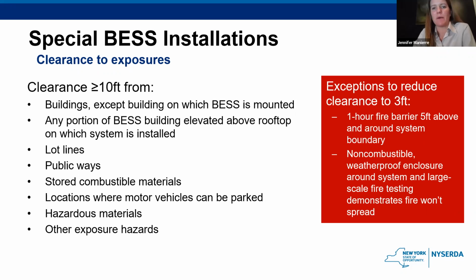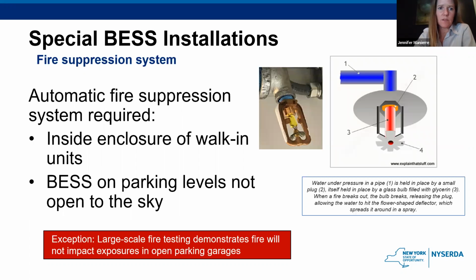Once again, you have the red box showing how you can get some exceptions to the code. Won't go through every single one of them. Fire suppression system requirements: they're required inside the enclosure of a walk-in unit or on parking levels that are not open to the sky, so anything other than the top level of a parking garage. Once again, there's an opportunity for an exception if large scale fire testing demonstrates that the fire will not impact exposures in open parking garages.